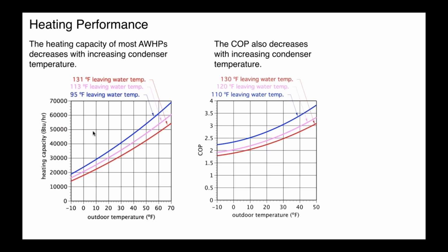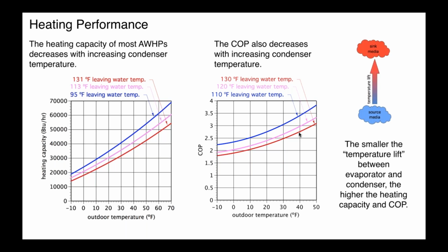The coefficient of performance, similar relationship here. The higher the water temperature, the lower the COP, and the lower the outdoor temperature, the lower the COP. And you can see an extreme condition here. It's 10 degrees below 0 Fahrenheit outside. We're trying to do 130 degree water. We're actually at about what? About 1.8 on our COP. If it was 40 degrees out, we'd be up around maybe about 2.7. Pretty significant increase.